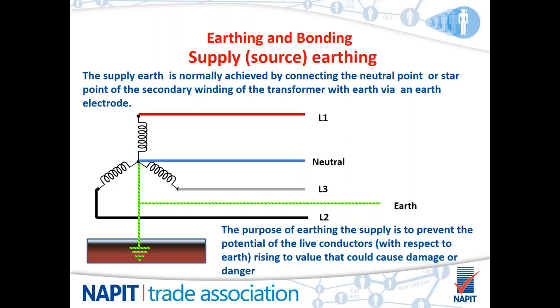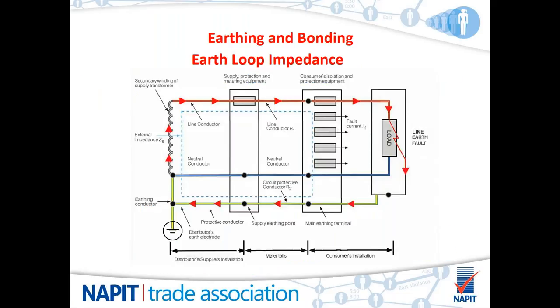The star point being 0 volts is the purpose. It is to prevent the potential of the live conductors with respect to earth rising to a value that could cause damage or danger. Because we have a 0 volts there, we can also put our synthetic neutral in for single phase systems. Okay, so in the diagram provided, we're showing the path for earth fault loop impedance. Now, the earth fault loop impedance is essential, as it causes the operation of your protective devices within the required time.